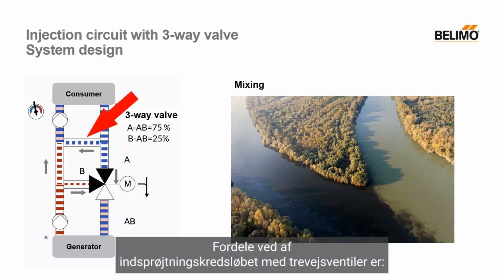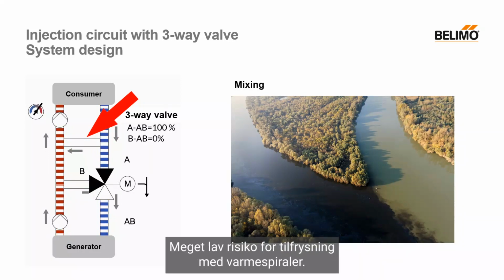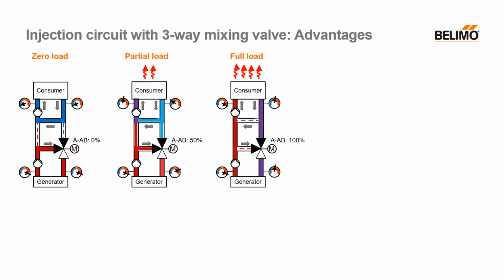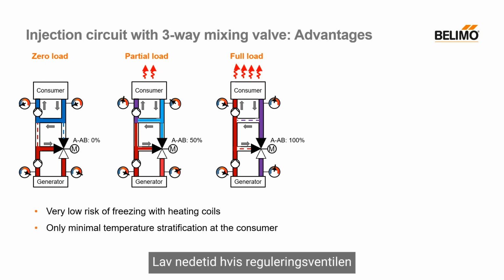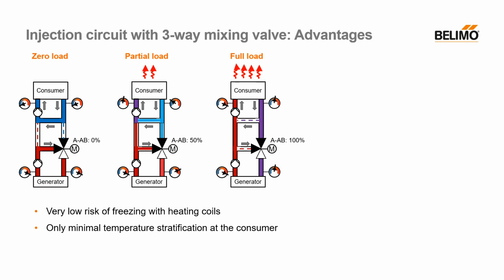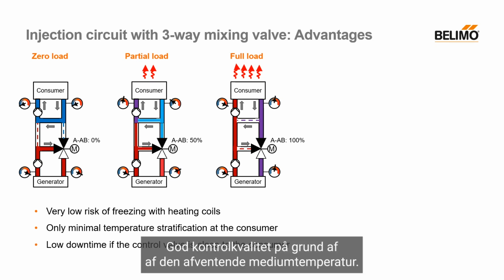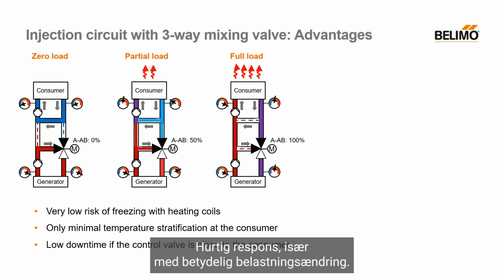Advantages of the injection circuit with three-way valve are very low risk of freezing with heating coils. Only minimal temperature stratification at the consumer. Low downtime if the control valve is close to the consumer. Good control quality on account of the pending medium temperature, quick response, in particular with significant load change.